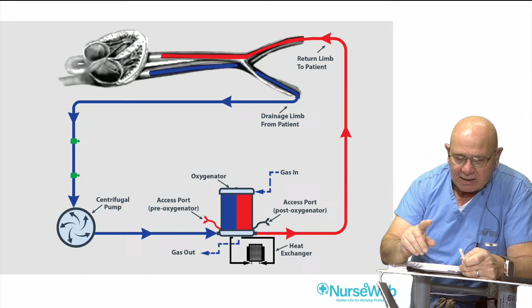And here you see stopcocks, and of course one of my lessons in our course is never, ever, ever connect a stopcock directly to a connector. Always use a pigtail, because if that breaks off, you're in a lot of trouble, and there's no repairing it. You have to replace it. You have to have a connector right there. It's going to be really bloody. You're going to suck air potentially. It's going to be very bad. Never, ever put a stopcock directly on a connector. That's one of the lessons you learned in our ECMO course.